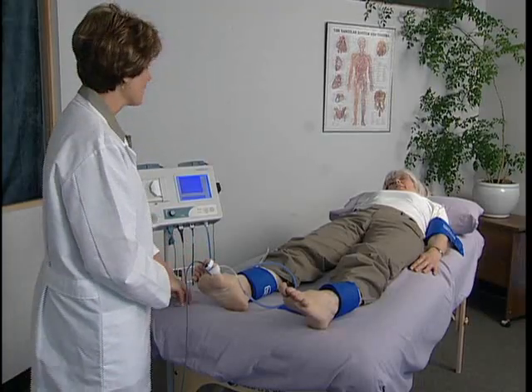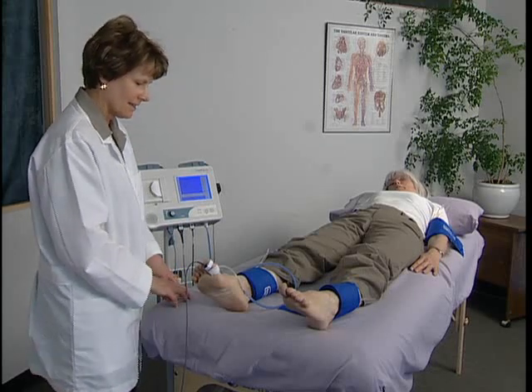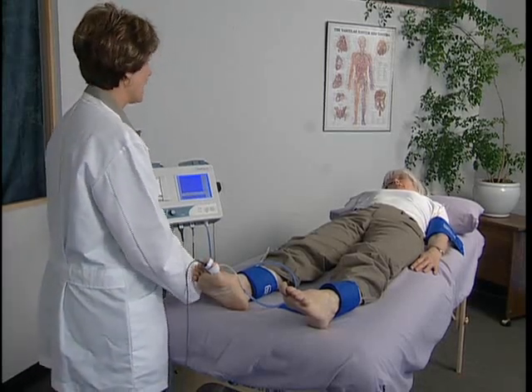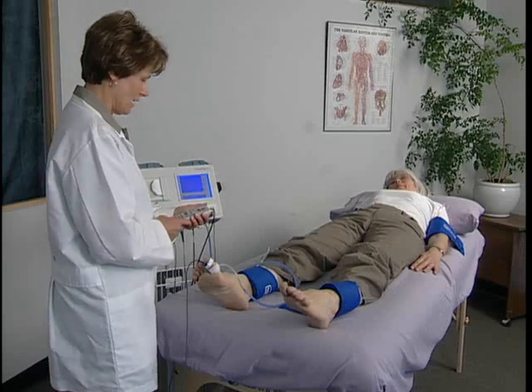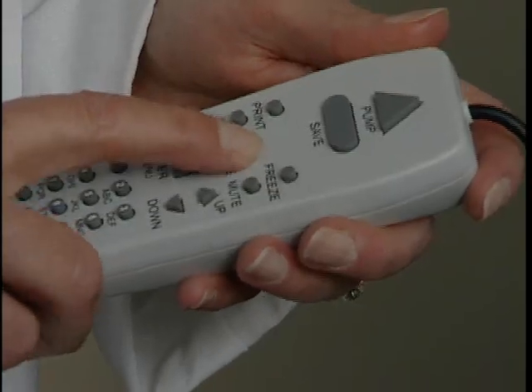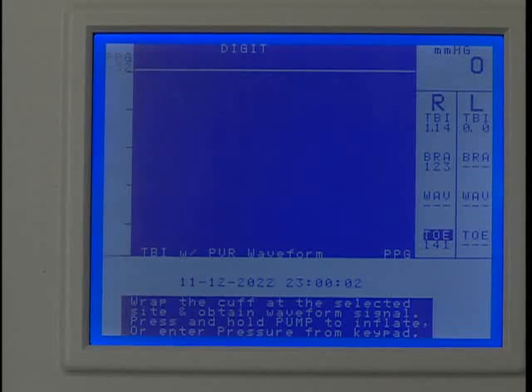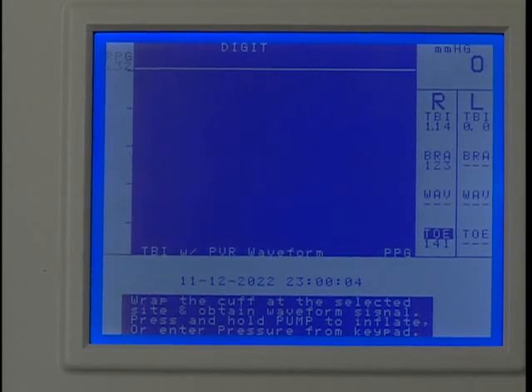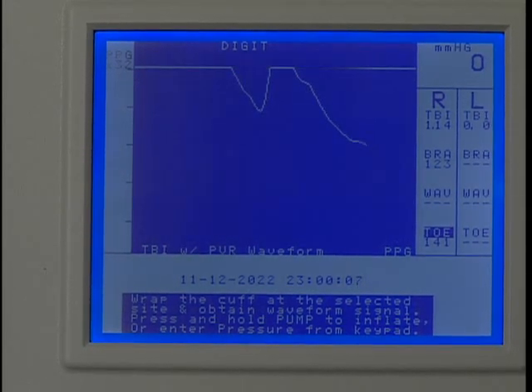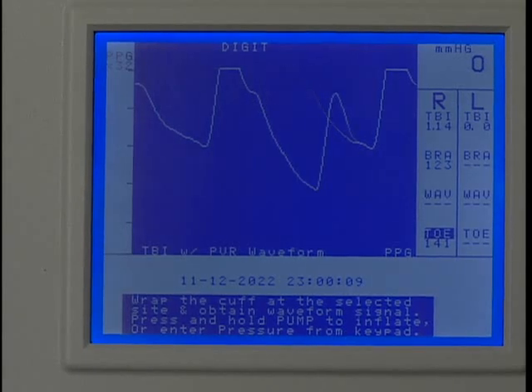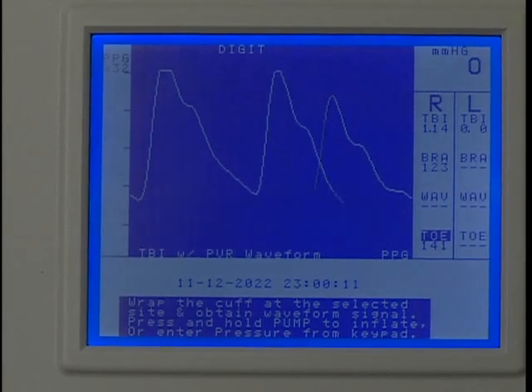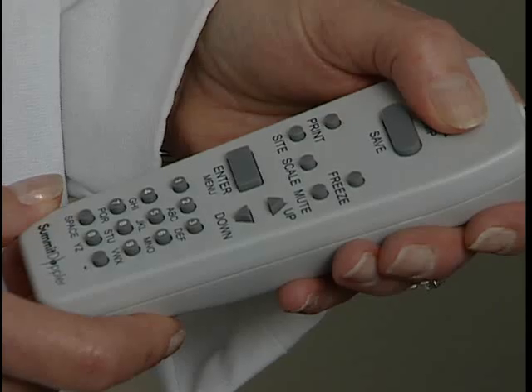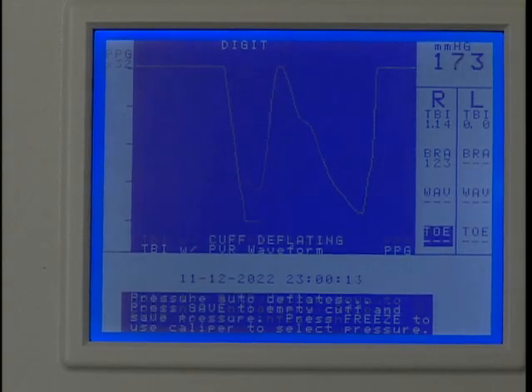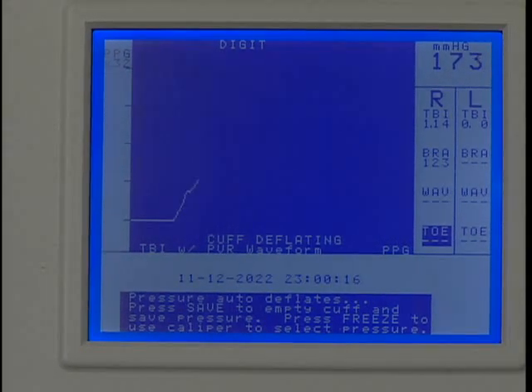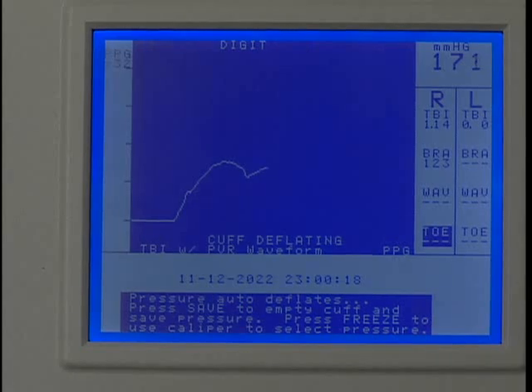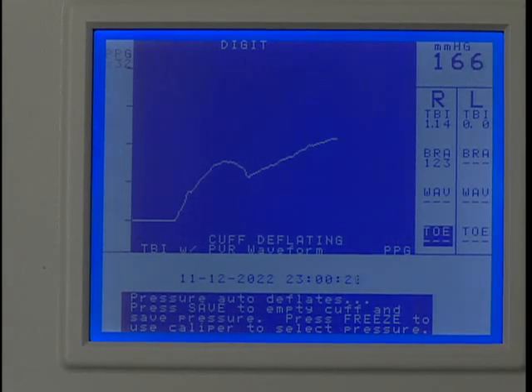The patient must be still to acquire a PPG signal. Wait a few seconds for the PPG waveform to stabilize after applying the probe. Press Scale one or more times as needed to adjust the vertical scaling to obtain a waveform as large as possible without clipping at the top. Once a stable PPG waveform is obtained, press Pump to inflate the digit cuff. Continue to inflate to a pressure approximately 20 millimeters of mercury above the pressure where the PPG pulsations disappear.